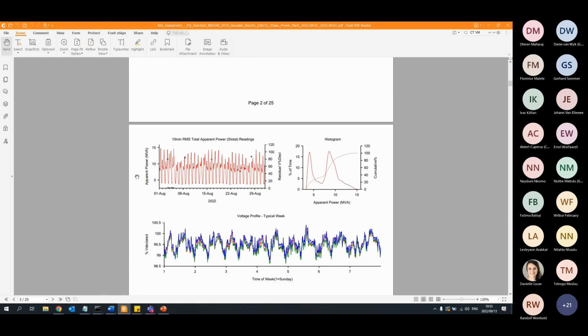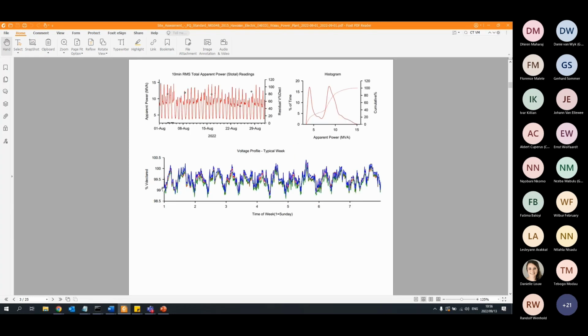Here we just show you the load on the system, and that will obviously impact the voltage regulation as well. We can see there are two working points for this specific point we're measuring in terms of the load. There's a lower value, most likely during the evening, and then a higher value close to 10 MVA load during the day. And then we can see how the voltage profile looks generally over a 7-day window.